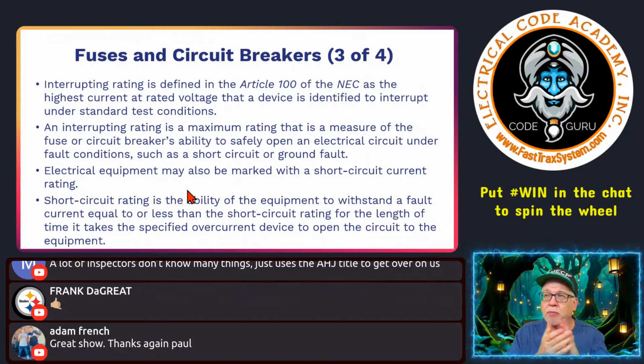Cooper-Bussmann, which is owned by Eaton. They have a really simple calculator where you put in the length of conductor, and always use infinite bus because you don't know anything different. Measure the length, put in the type of conductors you have, whatever. It'll give you an idea of what it is down at the equipment. And remember, the longer your conductors from the source, the available fault current is going to be less and less and less. It's going to go down as it gets further into the building.